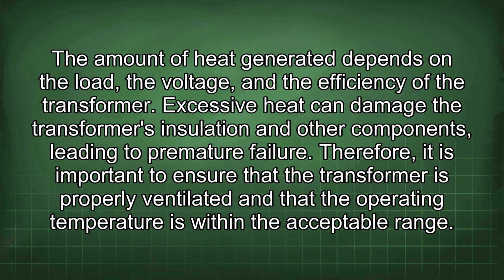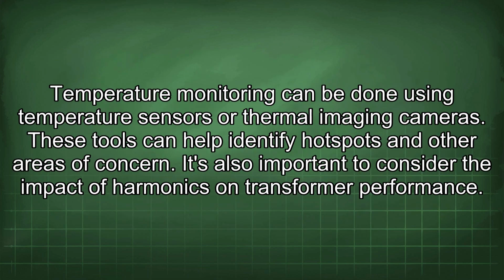Therefore, it is important to ensure that the transformer is properly ventilated and that the operating temperature is within the acceptable range. Temperature monitoring can be done using temperature sensors or thermal imaging cameras. These tools can help identify hotspots and other areas of concern.